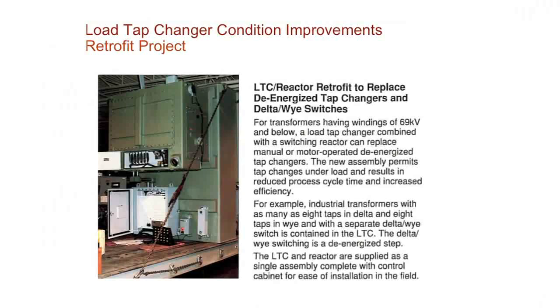Talk about an LTC reactor retrofit to replace the de-energized tap changer. In some cases, customers need to switch under what we call a de-energized, which is basically 69 kV and lower for us. It's called a delta Y switch, but you can change your whole transformer voltage on your high side with this type switch. It's a very similar type retrofit that goes on as a normal, what we call LTC retrofit.